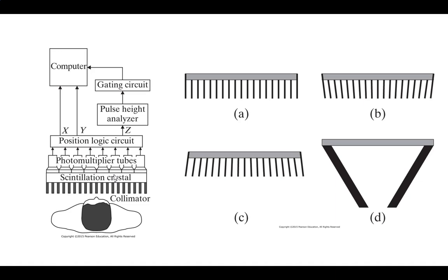That's the basic circuit. So on the right, you can actually see that the collimators could be a couple different things. The most basic is just straight in, right? But I could actually have them all narrowed in and aimed towards an area. Imagine if you were trying to concentrate on some small area within the body. By doing this, you're going to reduce some of the imaging problems, because since they're narrowed and aimed at that particular location, areas from different parts of the body won't interfere with it, and I'll get a very good direct shot.